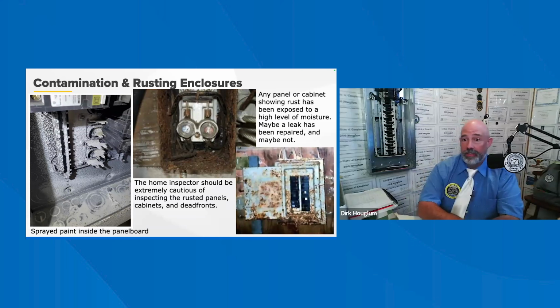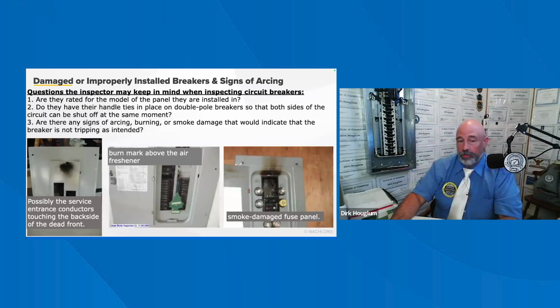In 2021, section E3404.7 refers to the interior of electrical equipment, the internal parts of the electrical, including the bus bars, wire terminal insulators, and the surface should not be damaged or contaminated by foreign materials. And that's why it's really good to, when you see rust, things like that, call that out. Just take pictures of it. Make sure you understand that this is a defect and it should be dealt with. We don't want anybody having problems. This can be a ticking time bomb.